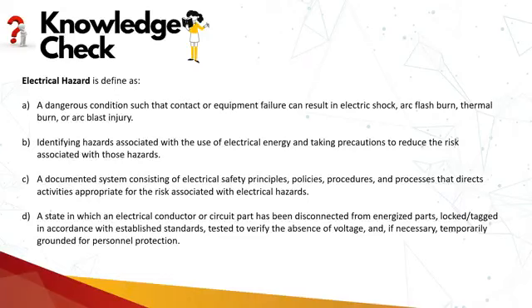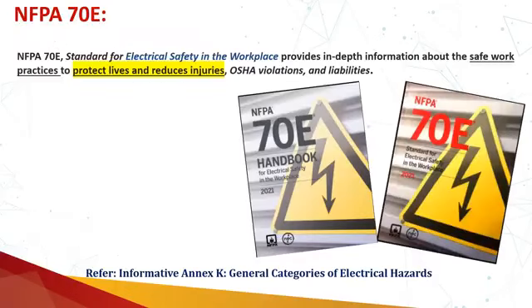So the electrical hazards covered in Annex K are related to electric shock, arc flash burn, thermal burn, or arc blast injury. So these are the four types of hazards covered in the standard. The NFPA 70E standard for electrical safety in the workplace provides in-depth information about safe work practices to protect lives and reduce injury, OSHA violations, and liabilities.